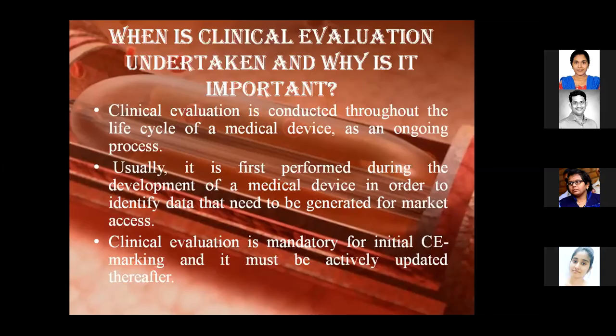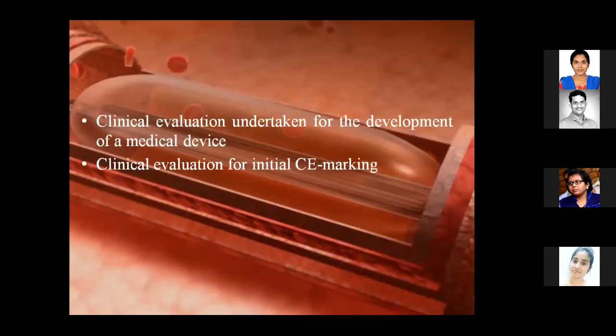Clinical evaluation is mandatory for initial CE marking and must be actively updated thereafter. Yes, sorry for interrupting. This is the main point, dear students. In order to get a CE marking, the device must be subject to a clinical evaluation in order to establish its safety. Yes, you can continue. Okay, sir.